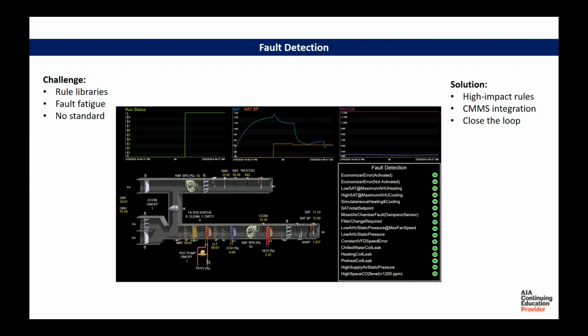Simultaneous heating and cooling doesn't need a lot of explaining. In some cases it does make sense, but you can program those out very easily. The vast majority of the time, you don't want your cooling coil and your heating coil open at the same time. So those are pretty clear examples of what I would call high impact rules that you would want to deploy across a campus, but there's a lot more that should be avoided.